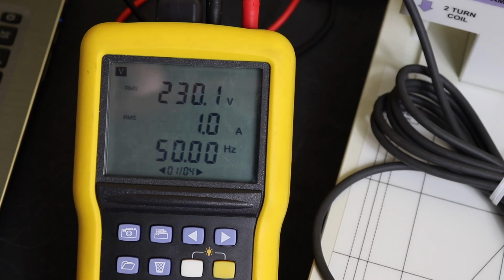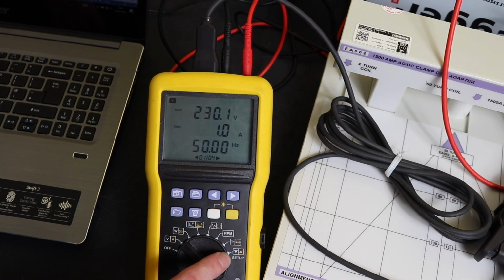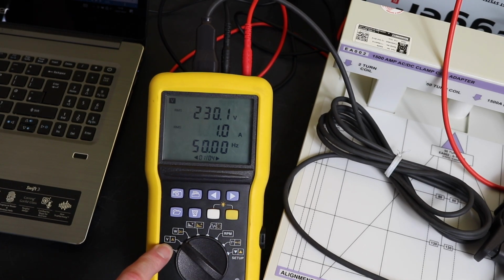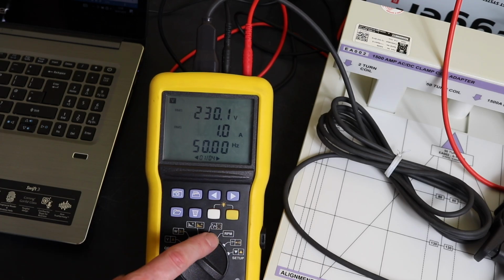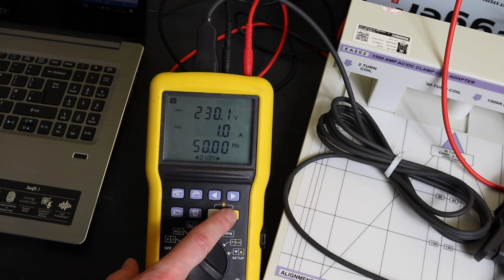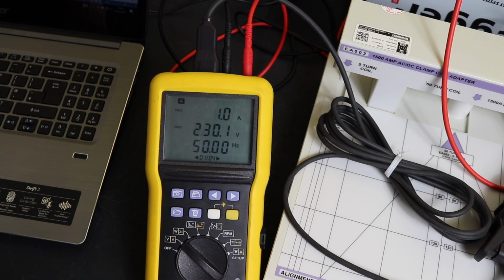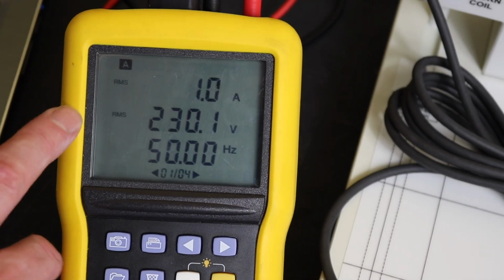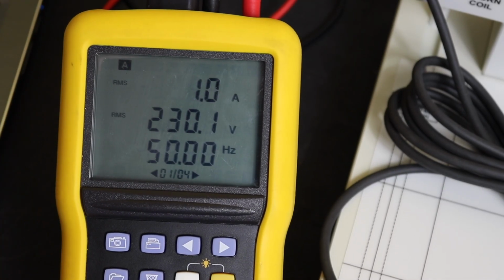All the positions on the function switch you see around here are dual functionality apart from the RPM. So the initial one we're on is volts and amps. To select between the functions, we've got the white key and the yellow key here. So I've hit the yellow key, then move to the amps, and zoom back in. So you get our voltage there, but we've got amps at the top, and we switch to amps on the screen there. And we go through the screens again.